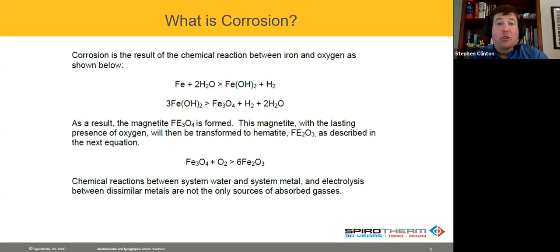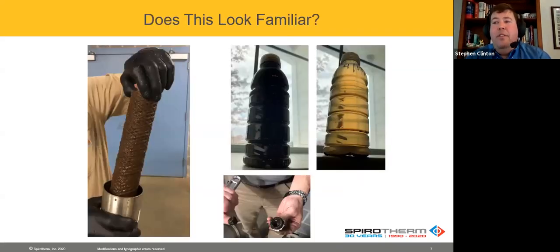The first we're going to hit is corrosion. You know, what is corrosion? Corrosion is basically rust. When you have oxygen, 20% of air is oxygen, it causes rust. That causes magnetite. You're hearing a lot of that in discussions, especially with some of the boiler manufacturers. There's not just rust, and there's magnetite, hematite, there are other particles. We need to let all of those separate out of the system. So corrosion is something we're probably more used to than some other things.